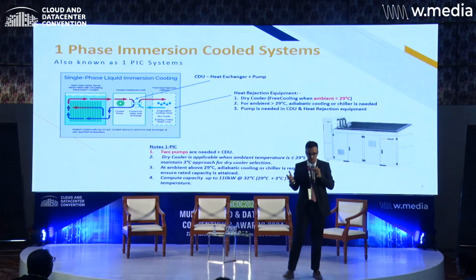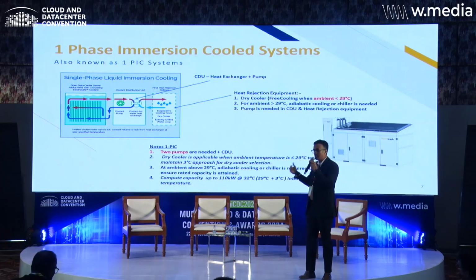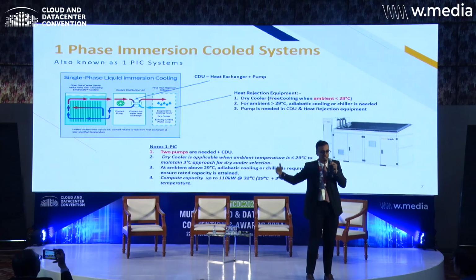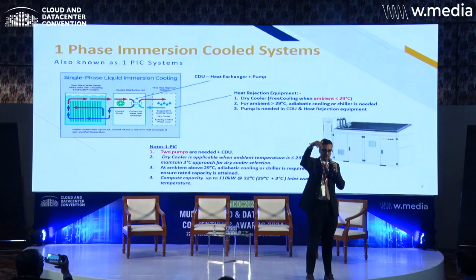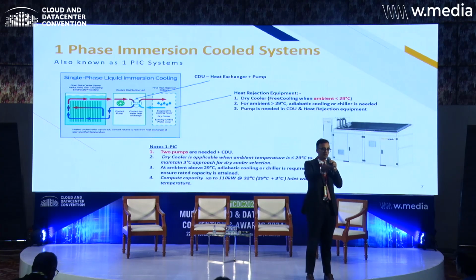This is the one-phase immersion cooling system. Basically, it is one phase. So it is pushing cold liquid at the bottom of the tank where the server is immersed, and it is cooling all the chips, and the hot liquid is getting out. So it's basically a push mechanism. You require an adiabatic cooler and you require a CDU in this case, unlike two-phase immersion cooling.